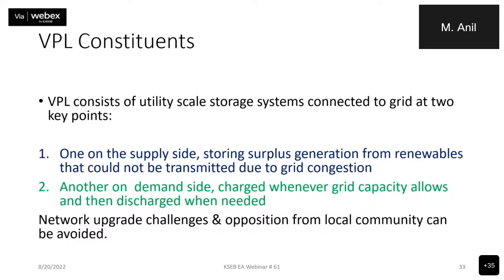And of course, it's up to you. If you go in for an upgradation of a 66 kV line to a 110 kV line, sometimes time is required to undertake the project. So during that particular time, the consumer is made to suffer. And also due to opposition from the public due to NIMBY syndrome and all, perhaps the time will get elongated without any bound. So that is another big problem with the upgradation of existing infrastructure. So existing infrastructure upgradation can be deferred with the VPL arrangement. That's a very important advantage of VPL.